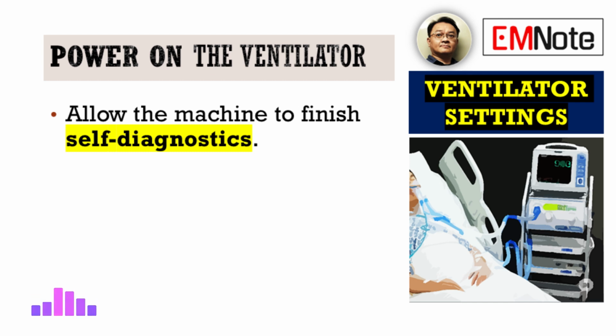interruption. This isn't just a quick flicker of lights or a beep, it's a comprehensive internal system check. The ventilator verifies everything: its internal circuit integrity, sensor calibration, alarm functionality, the lot. If it fails this self-diagnostic process, that specific machine is absolutely not safe for patient use. It signals a fundamental problem, something for biomedical engineering to look at. The successful self-test is an essential internal quality check, confirming the ventilator is ready for operation.